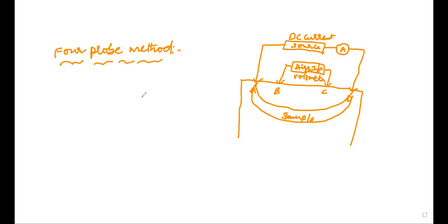The four point probe setup is shown in the figure. This consists of four equally spaced tungsten metal tips with finite radius. Each tip is supported by springs on the end to minimize sample damage during probing. The four metal tips are part of an auto mechanical stage, which travels up and down during the measurements.